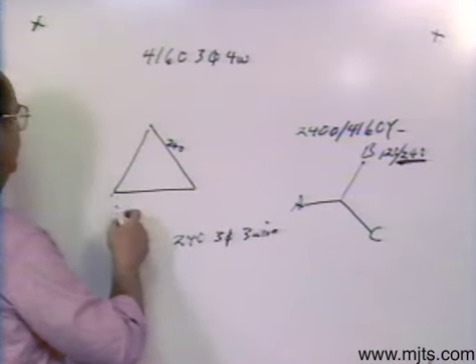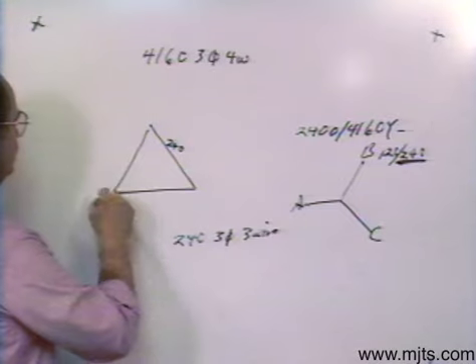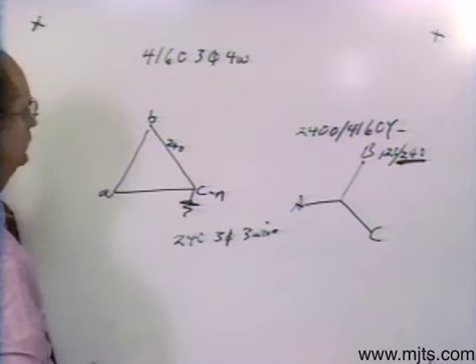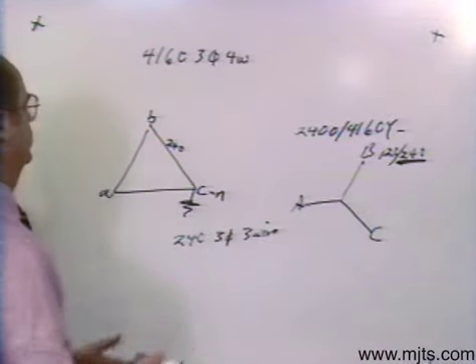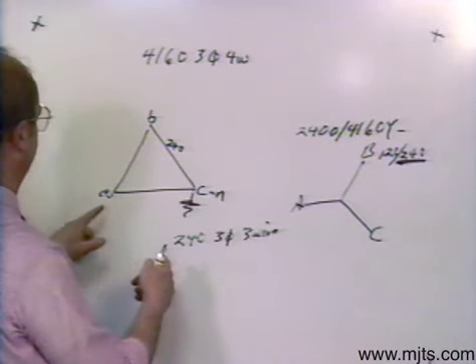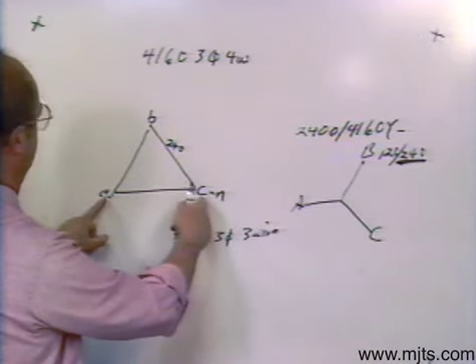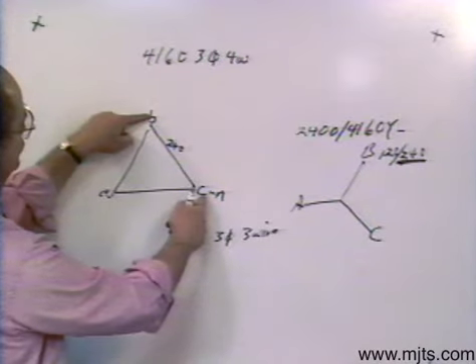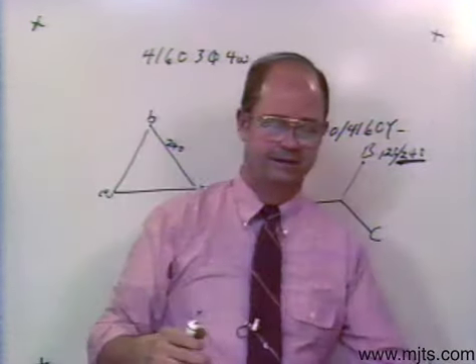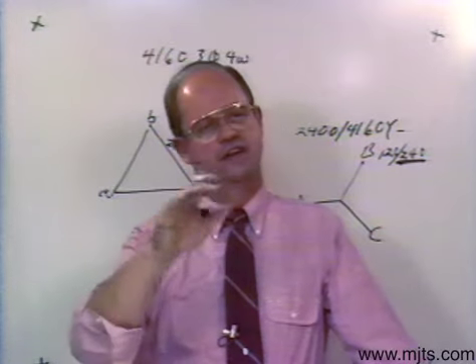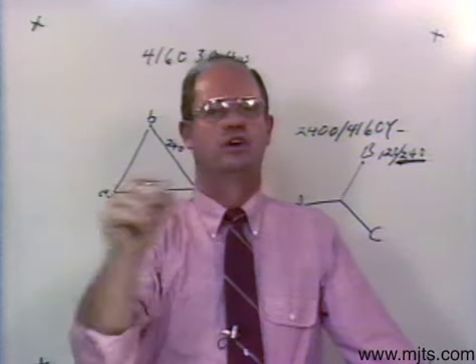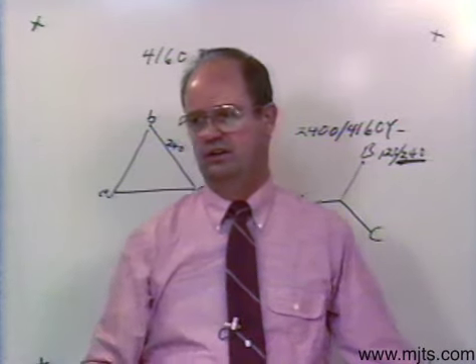It doesn't make any difference. Now if I turn around and say C is grounded — we've got A, B, and C — and we make this corner C grounded, that means I throw a ground on it right there. Voltage-rating wise, between my phases with that ground on there, I've still got 240 all the way around. A to neutral is 240, B to neutral is 240, but C to neutral — because C is grounded and they're tied together — then I've got zero. If it was a system with a delta and no ground on it, then I'd have no reference to ground, and any time there's no reference to ground, just draw a line through it.